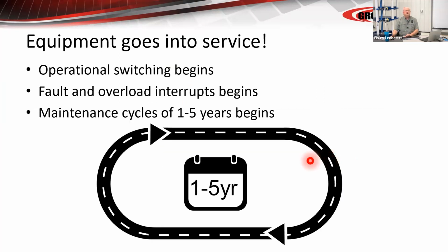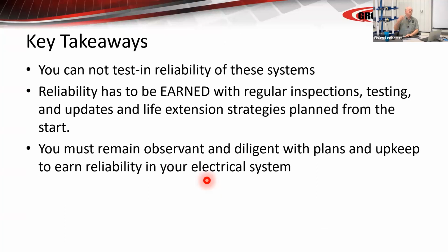So the equipment goes into service, and we're going to pick 5 years as a basic maintenance cycle. We're going to talk a lot about maintenance cycles in the last hour, but for right here, I'm picking 5 years. After 5 years, it's cleaned, it's maintained, it's serviced, it goes back into service for another 5 years, another 5 years, another 5 years, for 100 years. In that period, there are some times where there are upgrades and life extension programs to include the insulation, increase its ability to interrupt current, new insulation, new current carrying components, rebuild, overhaul. Also, we can talk about things we can do to the controls to improve the relaying and control.